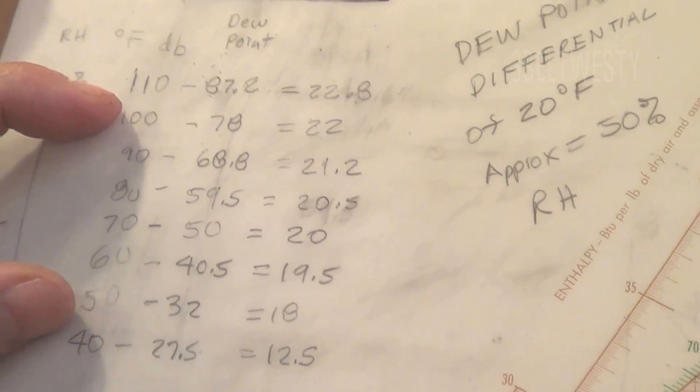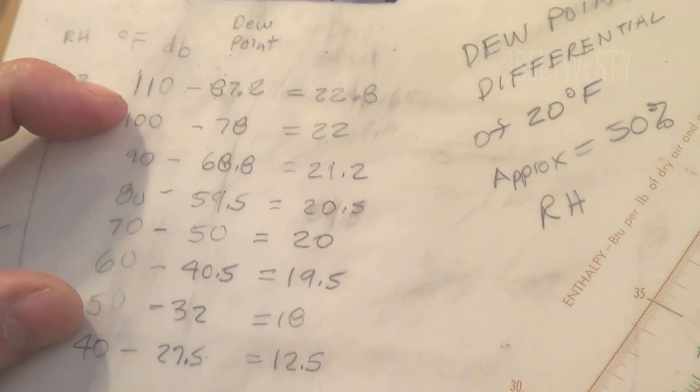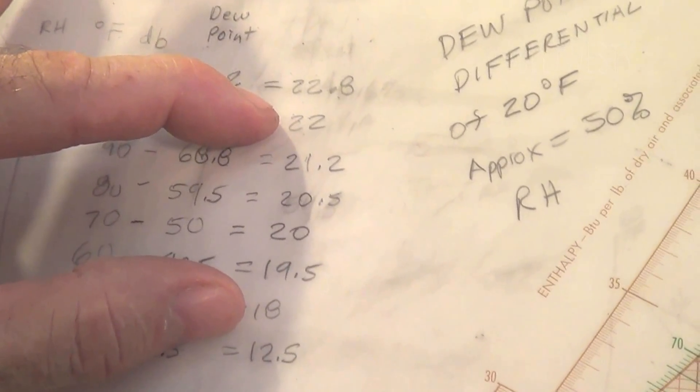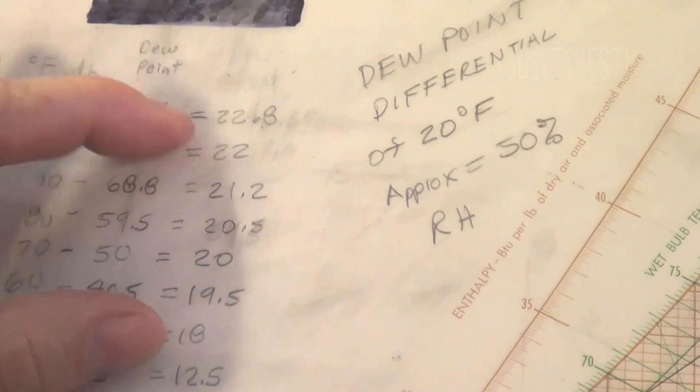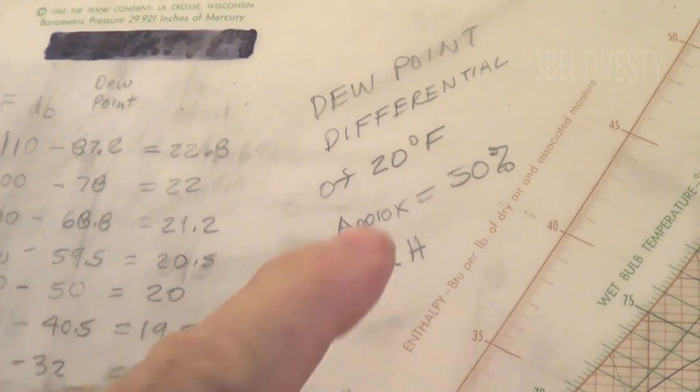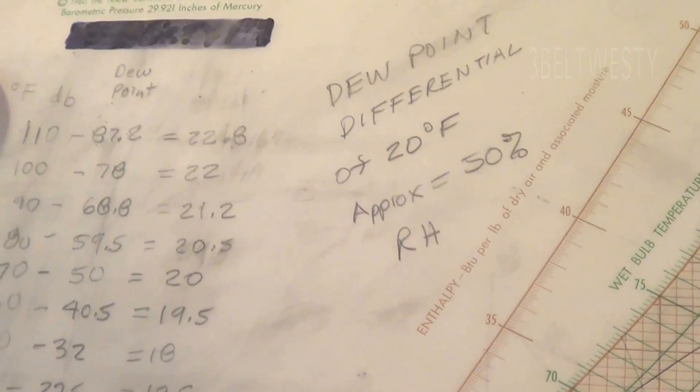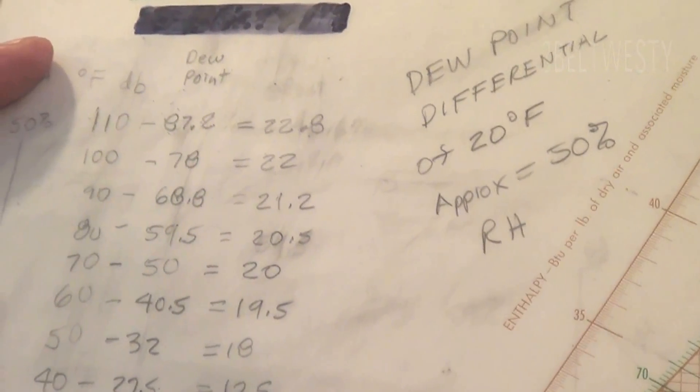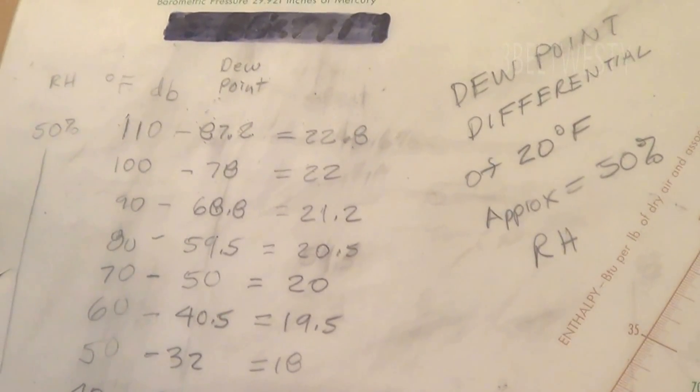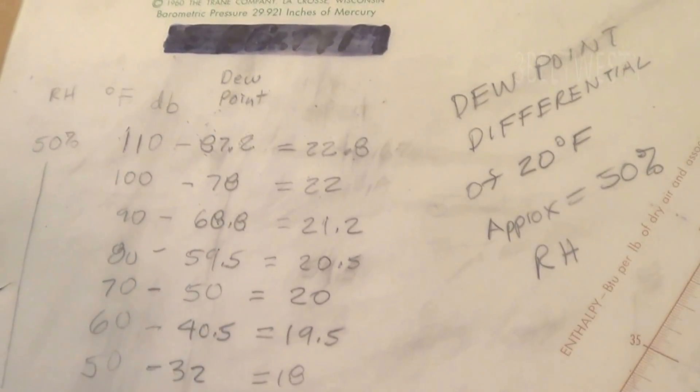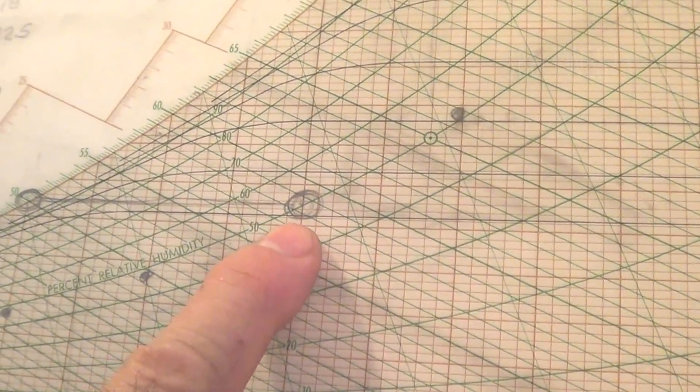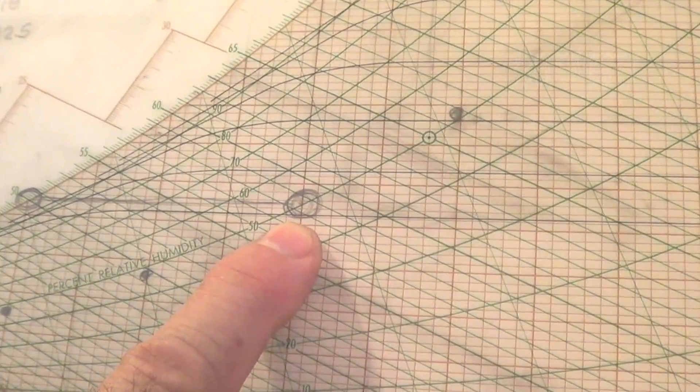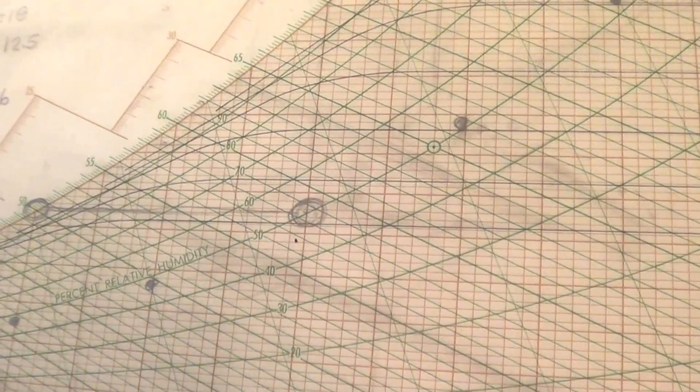So over a range of say 50 to 100 degrees Fahrenheit, you have about roughly a 10% error if you just assume that the differential is 20 degrees F. And this was actually used in some earlier control devices in HVAC because of this property of the 20 degrees F for 50% RH for controlling humidity. It's just kind of something the way it happened.